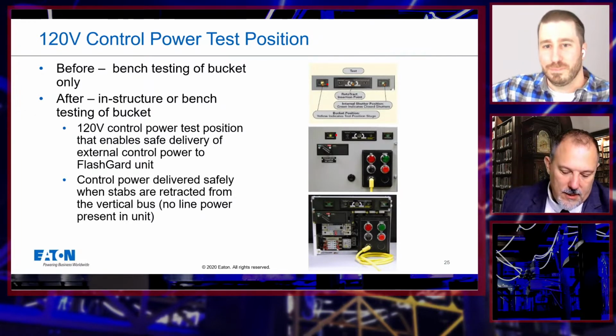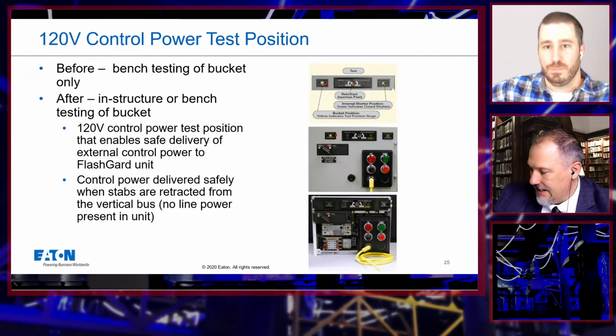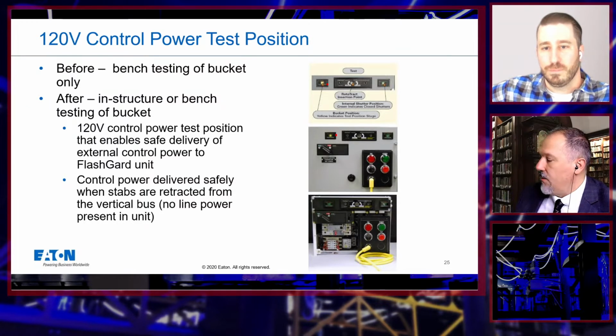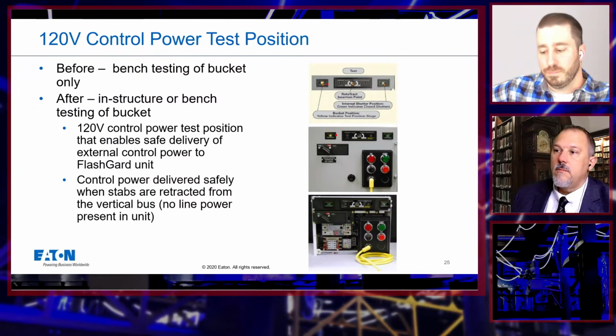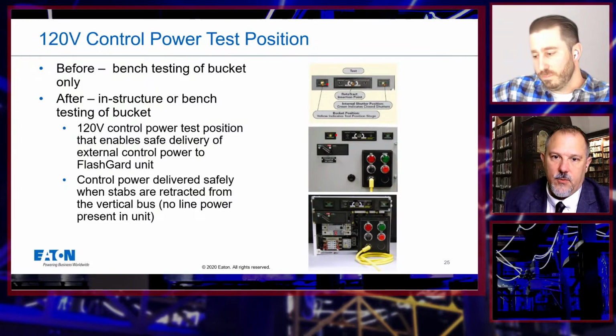What we're discussing, and what this whole program is about, is arc resistant equipment, which contains the arc. It's not addressing the aspect of reducing the arc flash. You could still have a 40 cal event, but it'll be behind the steel.